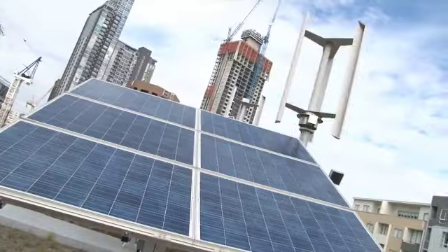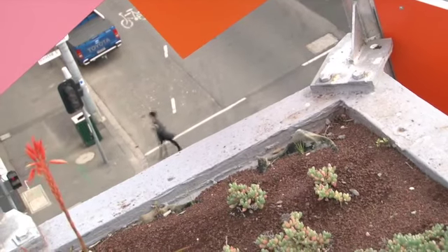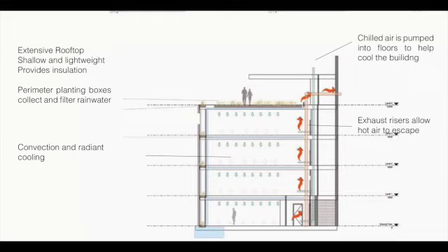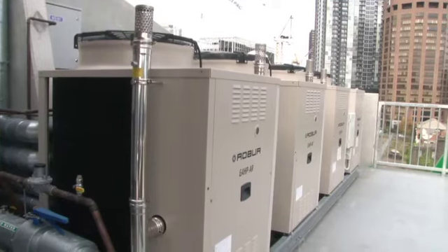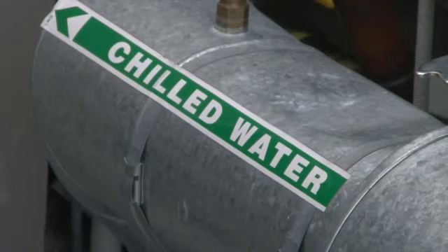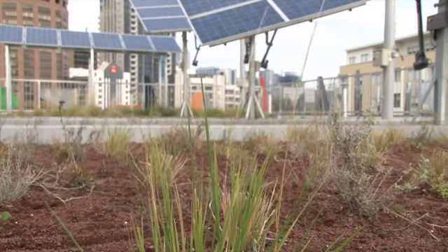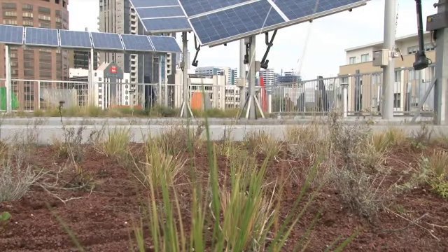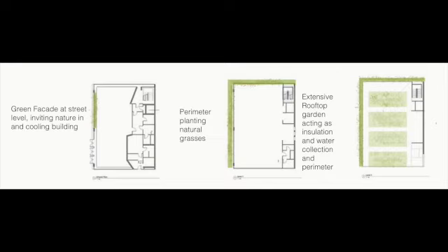The Pixel Building was Melbourne's first carbon-neutral building and utilises green techniques for heating, cooling and integrated greenery. It uses water pipes in the concrete flooring to cool the building radiantly and through convection. A heat exchanger preheats and pre-cools air coming into the building, and operable windows facilitate night purges. Extensive green roofs insulate the roof space whilst collecting water. Perimeter plantings also capture and filtrate water and aid with cooling the floors.